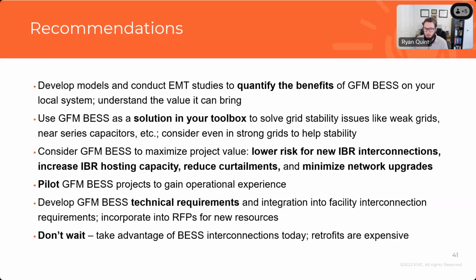What happens if I start putting GFM in areas that could otherwise run into stability challenges under N-1 or N-1-1, or even under extreme conditions? That helps you understand, visualize, and feel the value it could bring. It becomes a really useful tool in your toolbox to deploy in areas like weak grids or near series capacitors where you run into subsynchronous oscillation issues, but it can even help with and support strong grids, which leads to maybe wider spread adoption than just niche weak grid conditions.